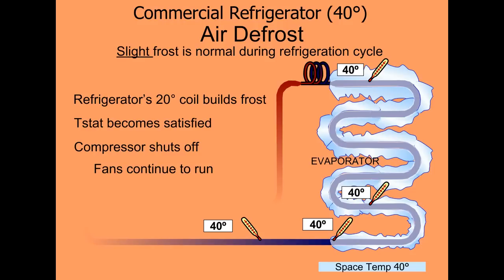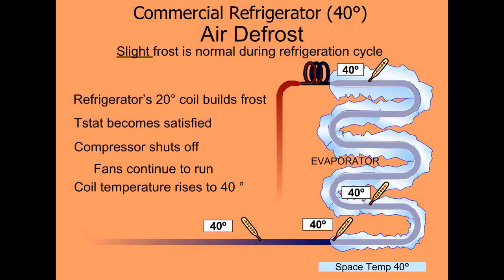If you ever walk in a refrigerator and the fans aren't running, you know there's a problem. The coil temperature does rise to 40 degrees eventually, and the frost melts off of there.